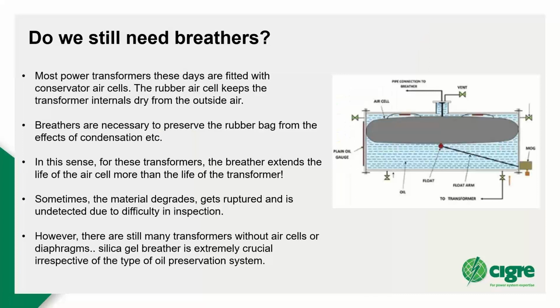I've been asked many times now whether we still need breathers, because the majority of power transformers these days have an air cell or a diaphragm. When you have the air cell, it keeps the transformer dry from the outside air, forming the first line of defense against outside ambient air, which may have oxygen or moisture. Technically, breathers are needed to preserve the rubber bag from the effects of condensation. So in a sense, breathers are the second line of defense, and they help extend the life of the air cell more than the life of the transformer. But sometimes, as Ivanka pointed out, the material degrades, gets ruptured, and it's sometimes difficult to detect during inspection. That is the reason why we still need breathers.